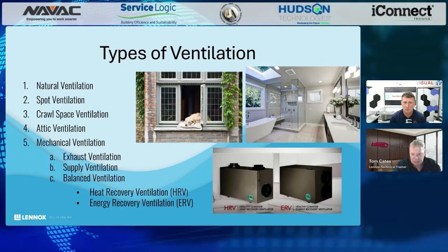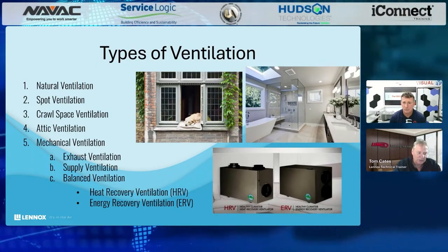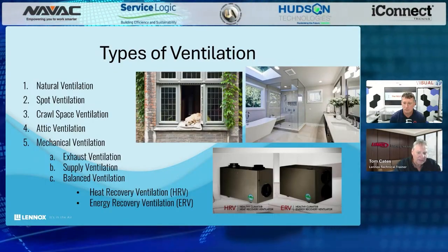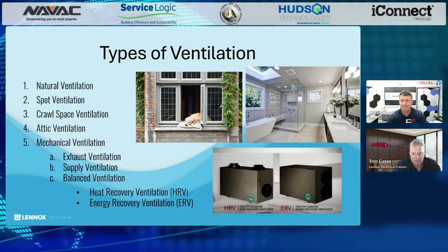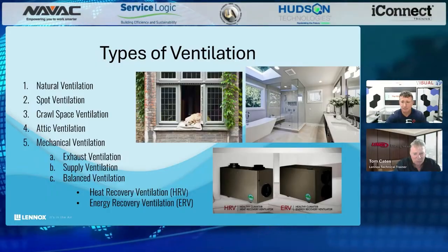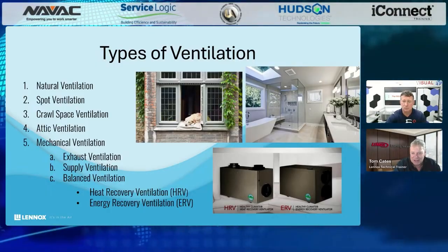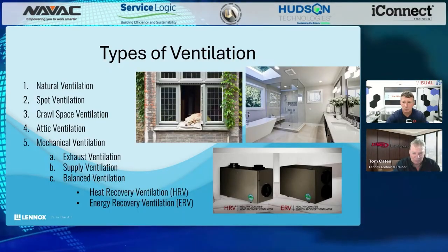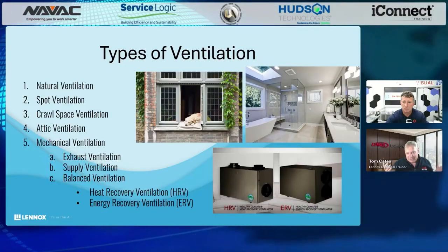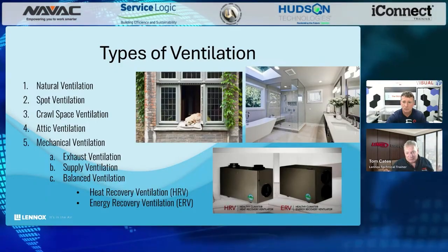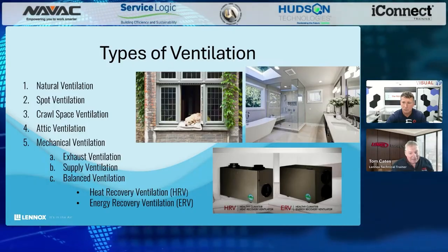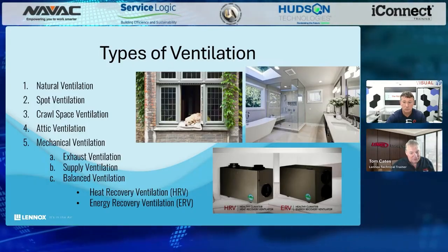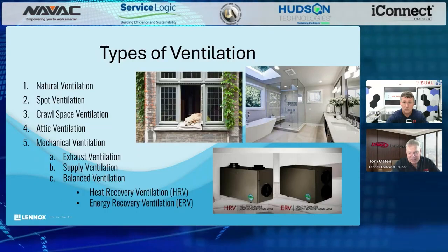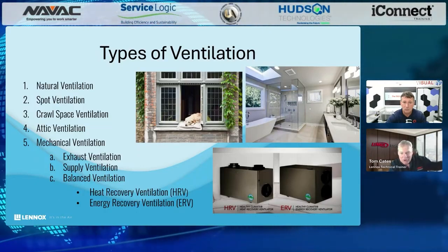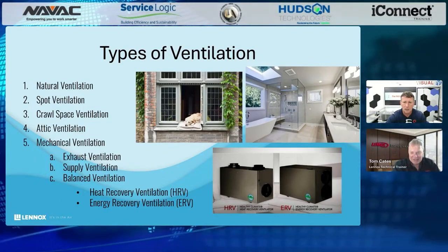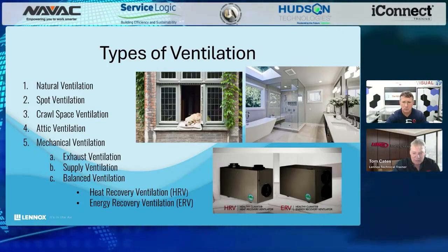Attic ventilation we sometimes see in areas where you're trying to reduce the heat that's in an attic, say in California or Arizona. Yeah, we do here. Sometimes, however, that can cause more problems than what it actually solves. We think we're solving a problem, that we're removing that hot 120 degree air of the attic, but now it creates a negative pressure influence, and the greater that negative pressure influence, the more that air moves across the building envelope. So we think we're fixing one problem, and you're actually creating an entirely new problem that may or may not even be recognizable.